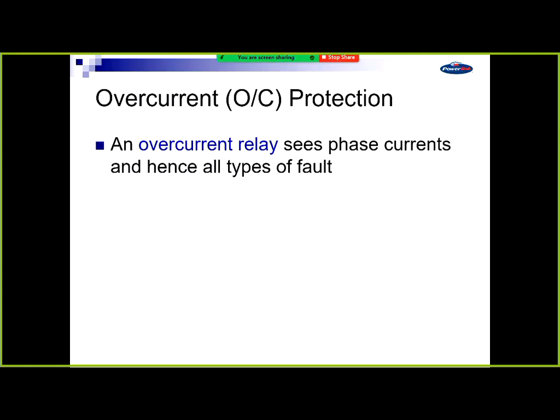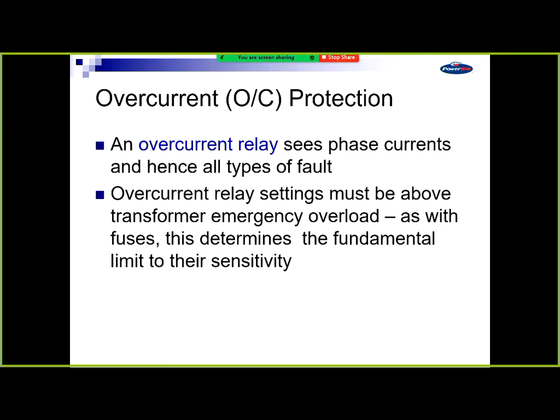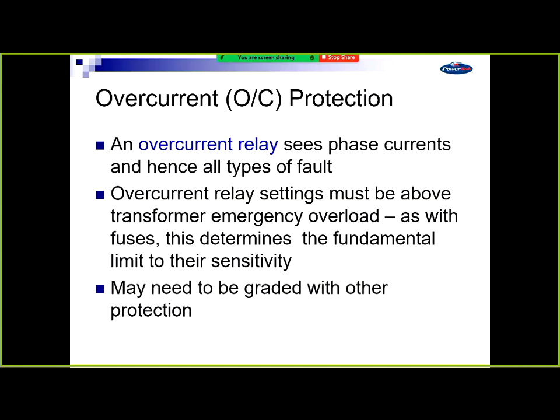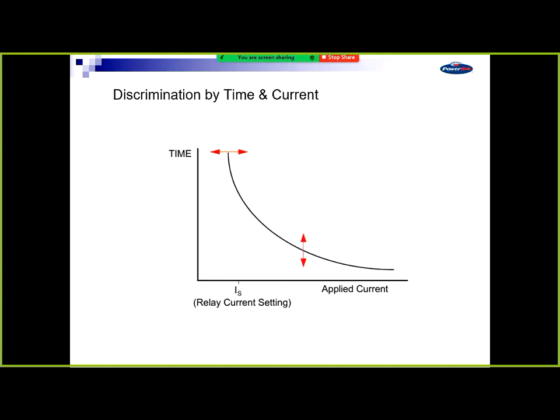An overcurrent only sees phase currents, so that limits its sensitivity. So you've got to grade it over top of load to be able to do that. And it may need to be graded with downstream protection as well, if you've got protection downstream. That IDMT curve is: get higher current, you go quicker. It's basically what it means. An inverse of that. Higher current means quicker time.